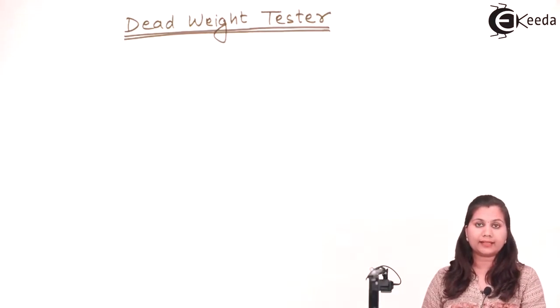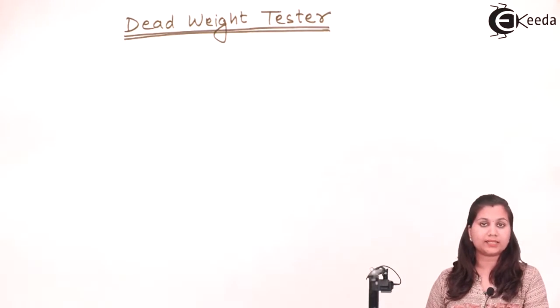As I have said, this device, the deadweight tester, is a calibration standard which is used for the calibration of pressure measuring devices such as pressure gauges.